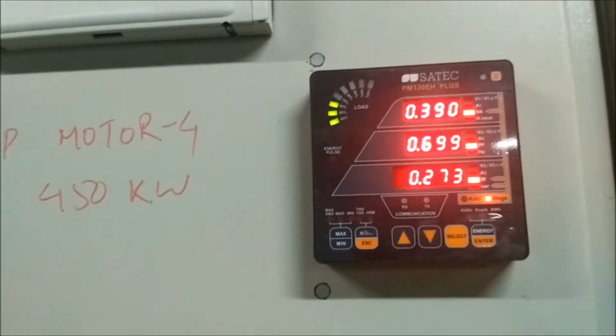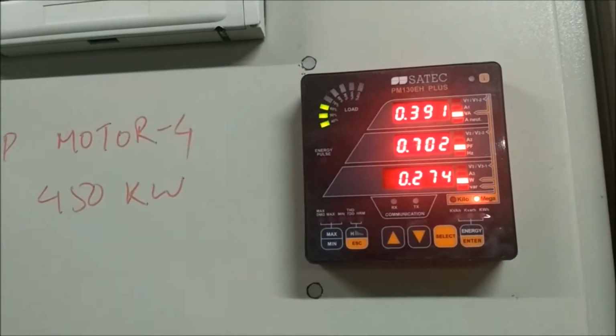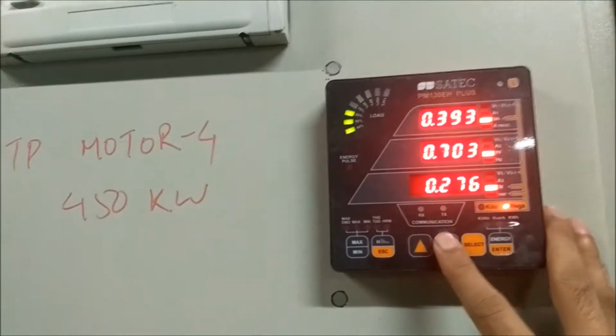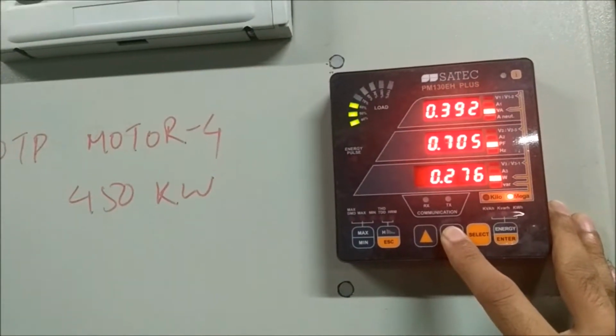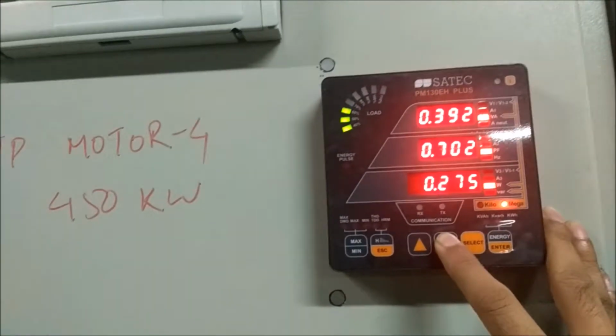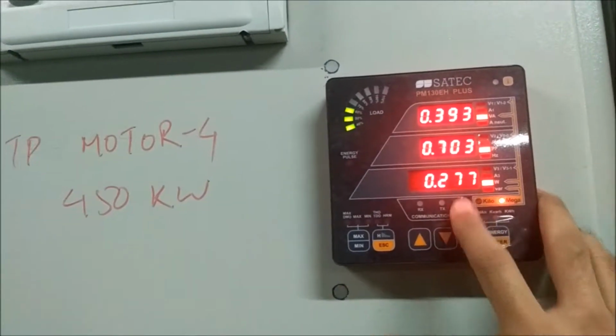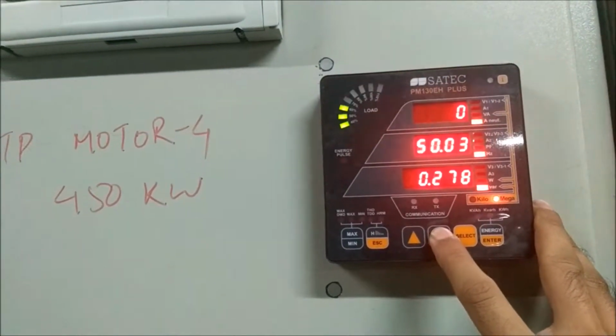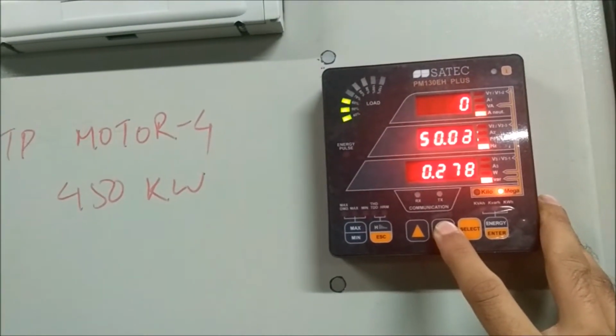Let me focus a little, and you will be able to see the apparent power and the power factor, and you are seeing the active power, that is 276, at which our motor is currently running. And this is the load bar graph, showing that our motor is running at 60% load.